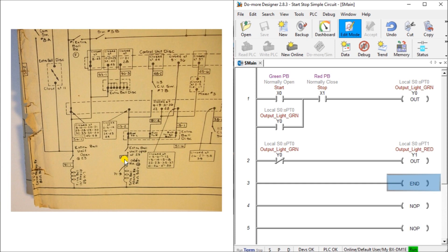Depending on the PLC used, the scan times vary from different manufacturers. For example, a 10 millisecond scan time will scan your PLC ladder logic 100 times per second or 100 hertz. A 1 millisecond scan time will scan your PLC logic 1000 times per second or 1 kilohertz.